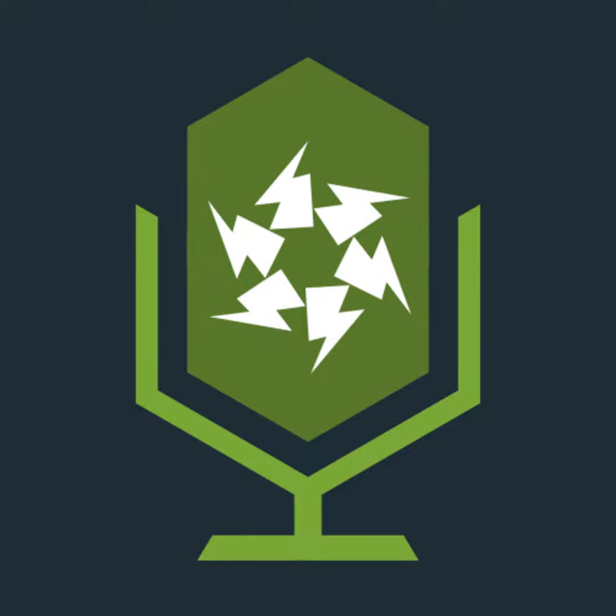All right. It then says, I'm back in 114.1 now. It then says in the paragraph below, for a supply in accordance with the ESQCR, it should be deemed that the connection with Earth of the neutral of the supply is permanent. So it's not temporary, it's not bolted, it's not screwed, it's a permanent connection.